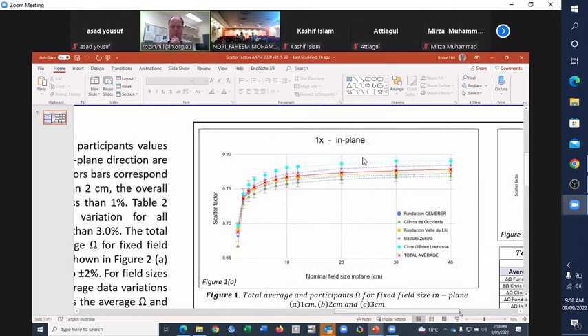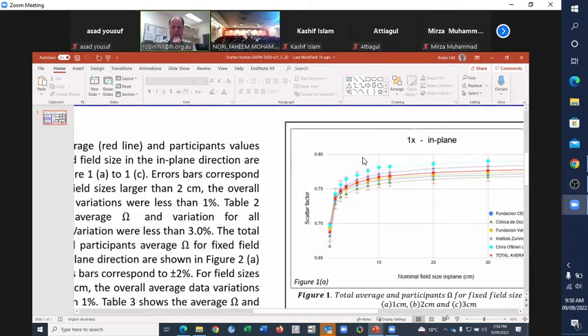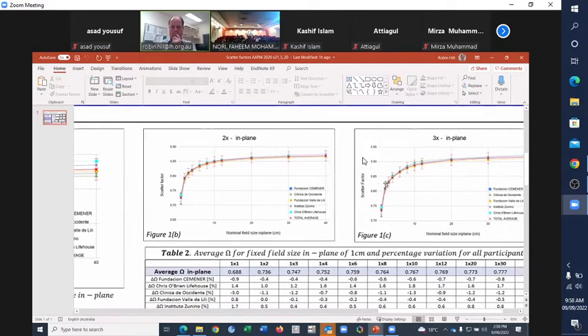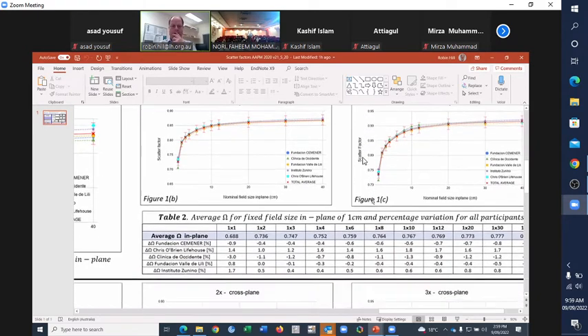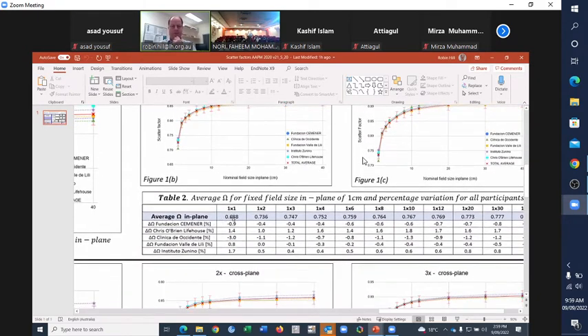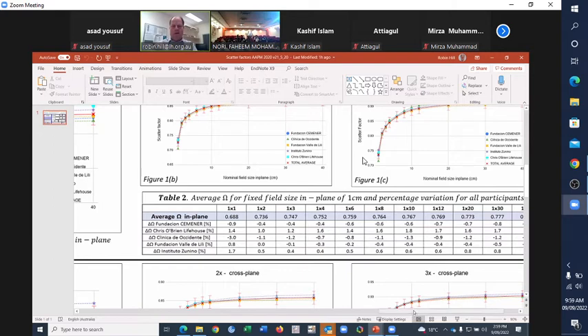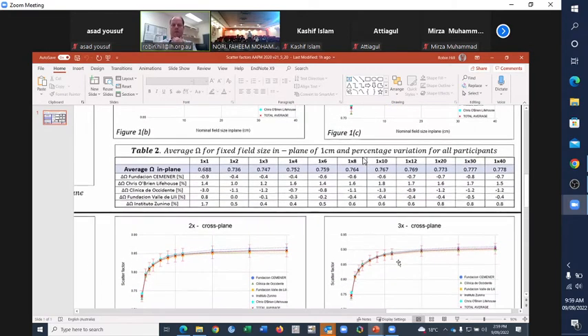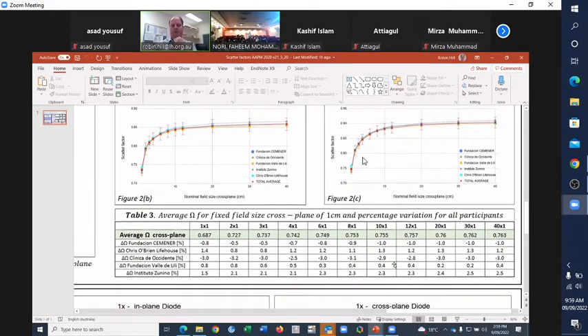That's the one by one. Once you go up to the two by two, you get a pretty similar result. When you get up to starting at three centimeters, about three by three, you can see the agreement is really quite good. Here are the average values, the difference for field sizes, the percentage difference for all of those. There's nothing in these results that said to us that any of us were doing it wrong, because we are treating SRS. It's actually a really nice useful exercise to be able to compare all of that.